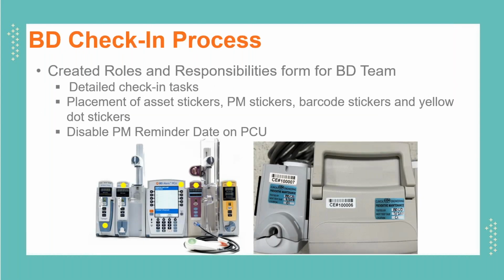So prior to BD coming on site, we created a roles and responsibilities form for them. That detailed some of the check-in tasks they were going to be responsible for, and that included the placement of a lot of the stickers we were going to have on there. That included the CE sticker that we have here, the preventative maintenance sticker, the barcode stickers for the integration on the LVP pumps and the syringe pumps. And then those yellow dot stickers we utilized were going to indicate that that was a new pump in the fleet, a signal for everybody.